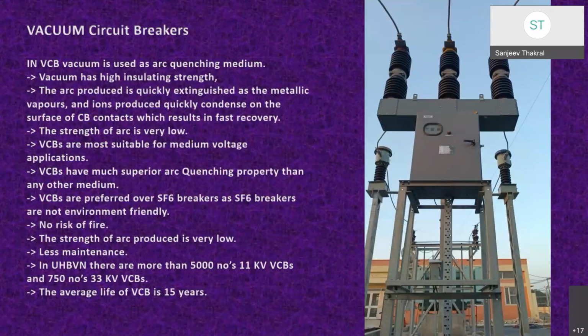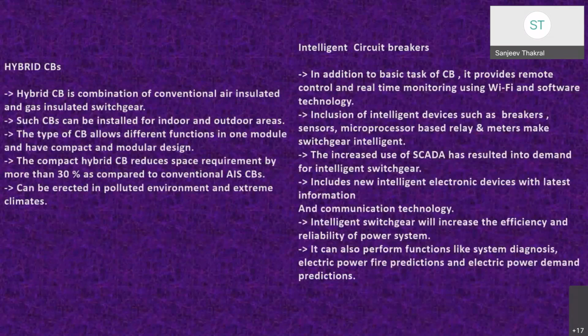A hybrid circuit breaker is a combination of types of circuit breakers and can be installed for indoor and outdoor areas. It allows different functions in one module and has a compact and modular design. The main advantage of compact hybrid circuit breakers is that their space requirement is more than 30% less as compared to conventional air circuit breakers. These can be erected in polluted environments and extreme climates, and their erection time is also very short.